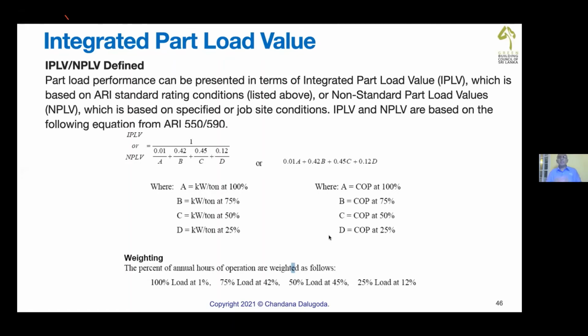So we call it a part load intensive application. Some buildings are almost at full load but slightly on part load, like office buildings. If a building operates 24 hours, definitely it has part load operation. So the efficiency is also given as part load. We call it integrated part load value. We'll have to check that as well.